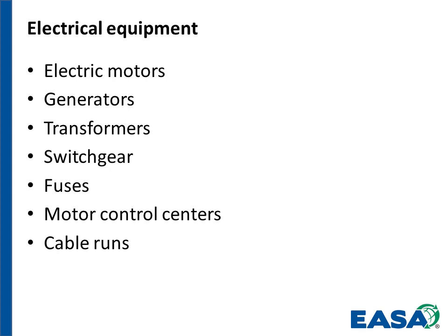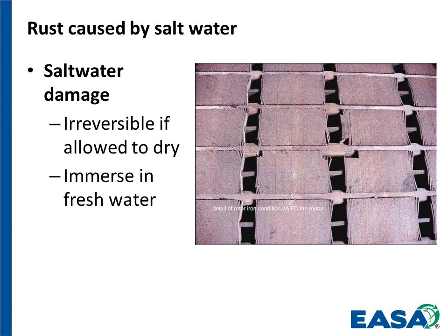So if we look at electric motors, if it's a rust issue caused by saltwater, when we look at a rotor and the stator core, if we have saltwater penetration and the salt water is allowed to dry, then the salt is there to stay. We can clean it and soak it, but the rusting process that's started by that salt water being soaked into the cores is irreversible. So yes, we can clean this very large electric motor, dip and bake it, and get it back into service with new or refurbished bearings. However, we have to recognize that the rusting that we're looking at in this picture is irreversible.